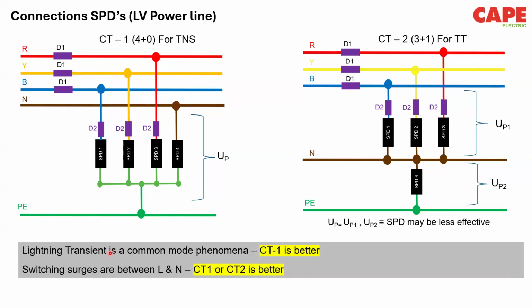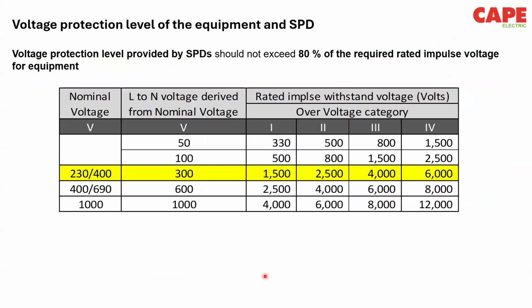So for lightning transient in common mode, CT1 is better. And for switching surges between line to neutral, CT1 and CT2 is better. Now I've already shown you this in another form in the previous slides. So we have class 1 is 1.5 and class 4 is 6 kV.